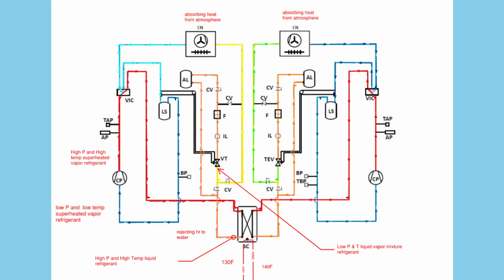The refrigerant vapor flows through the four-way reversing valve again. From there, it is directed to the liquid separator, also called a suction accumulator, which protects the compressor by ensuring only vapor, not liquid, enters the compressor compartment. The refrigerant is then returned to the compressor suction port, where the cycle begins again.